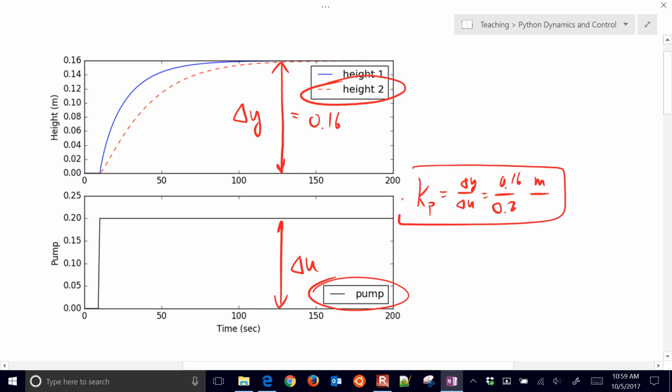But there's our gain. Okay, and then we go with a time constant and time delay. So the very first thing I'm going to do is look at the inflection point, okay, where that traces down, where the step started was right here. And so there's just a little bit of delay, not much. It's about zero. Maybe this is going to be something like maybe 1 to 5 seconds. Okay, so I'll put down about 2 seconds.